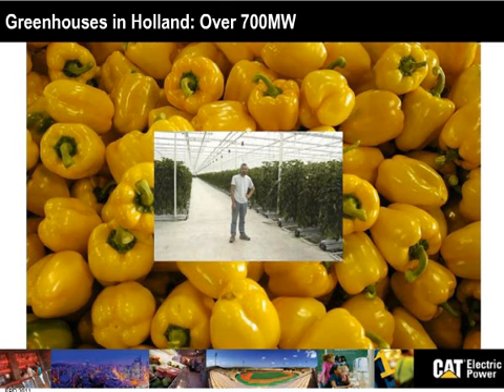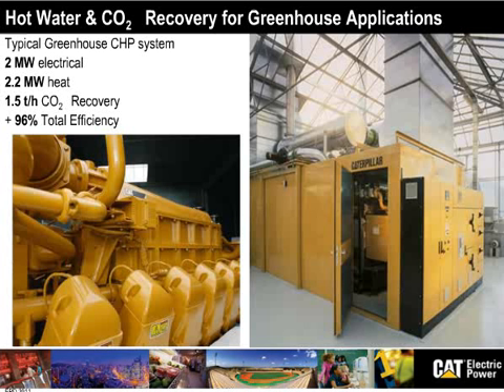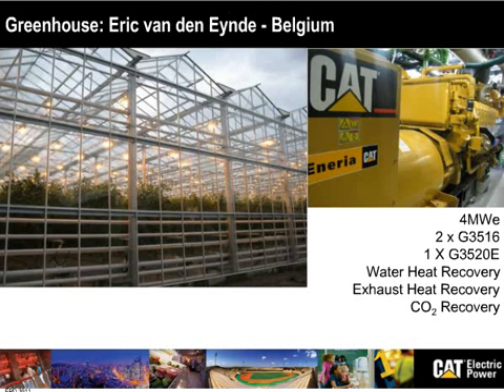Typical greenhouse in Holland, you can see here, 2 megawatt units producing 2.2 megawatt of heat, 1.5 ton of CO2 per hour, and the efficiency of the system is above 96%. That's a very good deal for the growers in the greenhouse. Here another one in Belgium. This is a combined system with 3 gensets at 4 megawatt total. And I hope you see on the screen the lights that the genset is powering, and the heat is recovered, so is CO2.